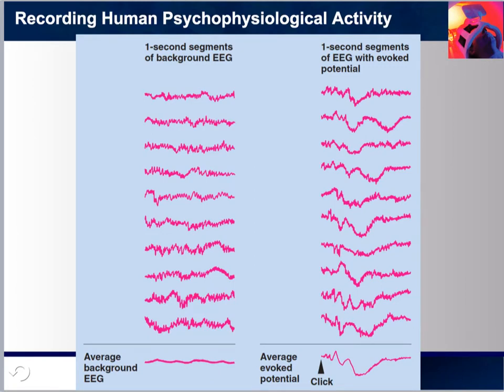In this figure, we are able to see the cortical EEG that follows a sensory stimulus, and how it has two components: the response to the stimulus, which is the signal, and the ongoing background EEG activity, which is the noise. The signal is the part of any recording of interest; the noise is the part that isn't. The problem in recording sensory-evoked potentials is that the noise of the background EEG is often so great that the sensory-evoked potential is masked — like detecting a whisper at a rock concert.